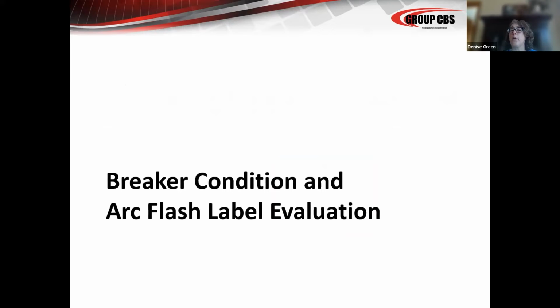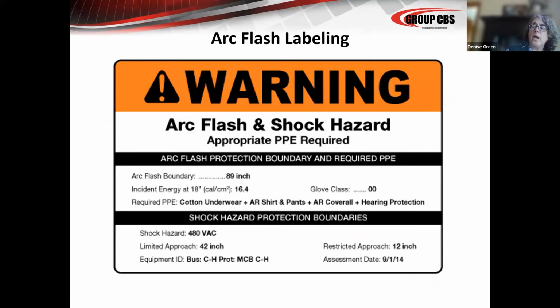Now we're going to talk about the breaker condition and evaluating labels. We're going to talk about the 1584. It's really important, when your technicians are standing in front of the label and they're looking at that arc flash boundary of 89 inches and what the incident energy is, to keep in mind how was that equipment maintained? Has it ever been maintained? Has it been installed for 25 years and no one has ever opened up the door?